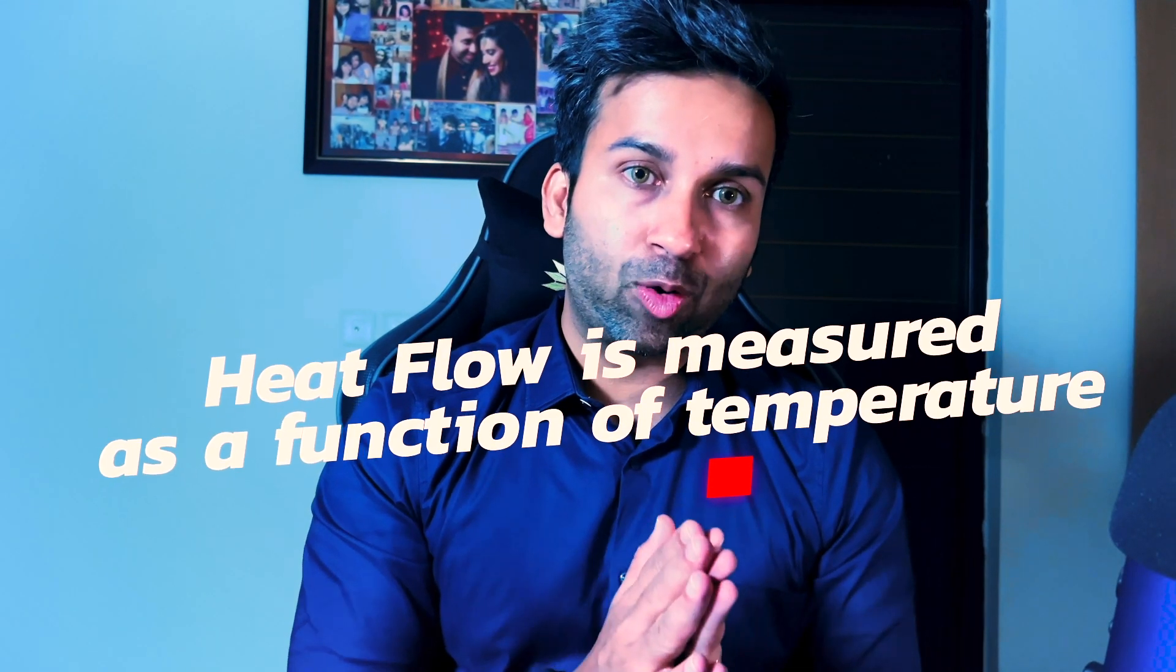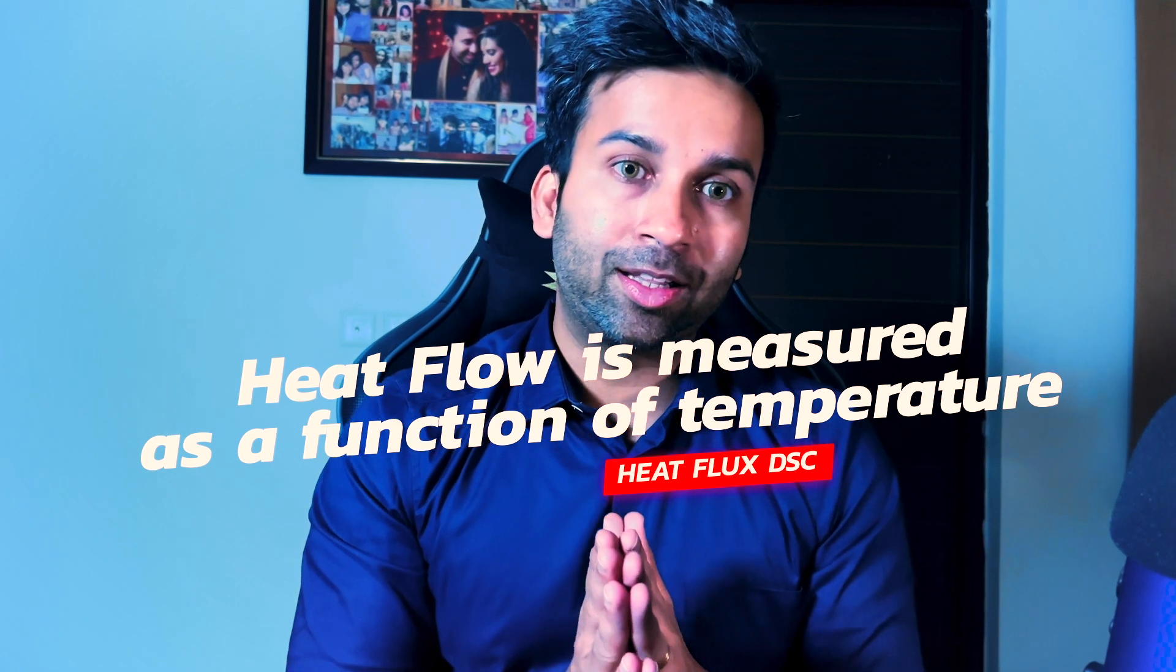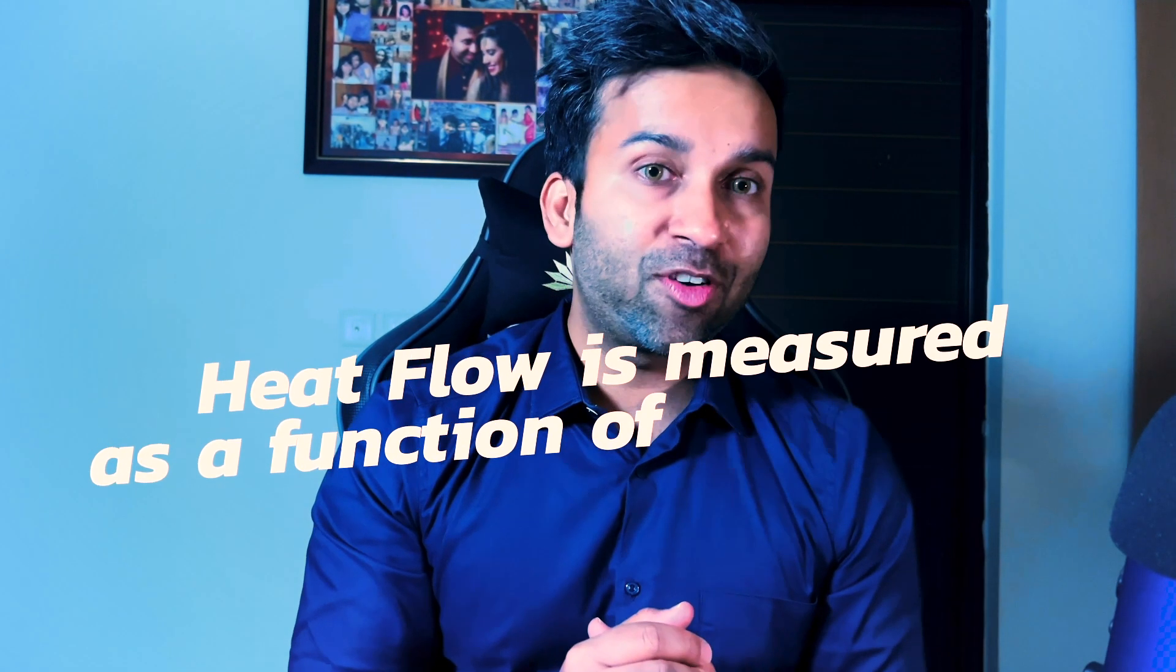There are two main types of DSC. Heat flux DSC is a type where the heat flow into or out of the material is directly measured as a function of temperature. This is in contrast to power compensated DSC where the temperature difference between the sample and reference is kept constant by adjusting the power supplied to the sample.